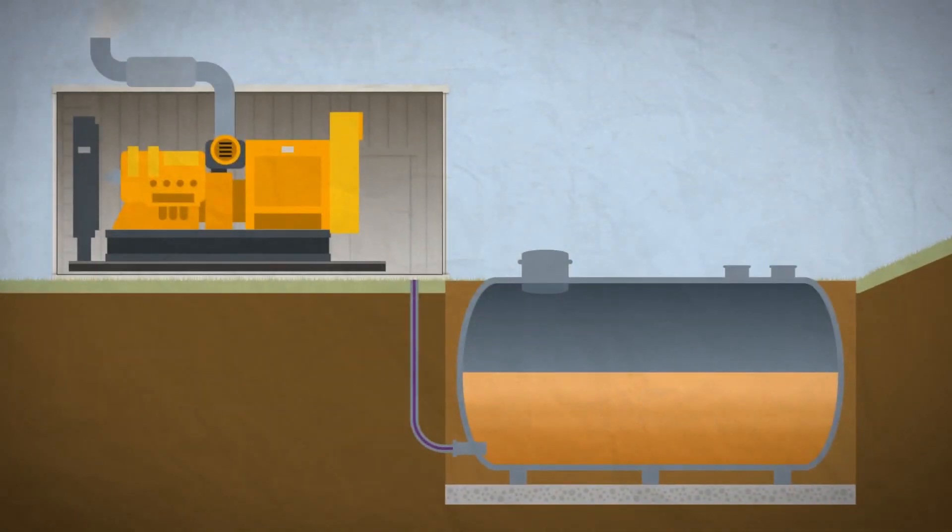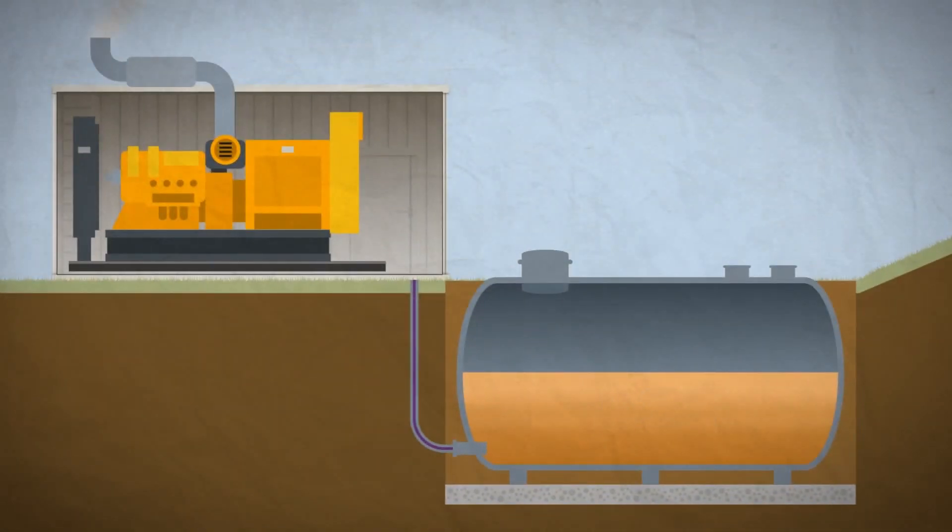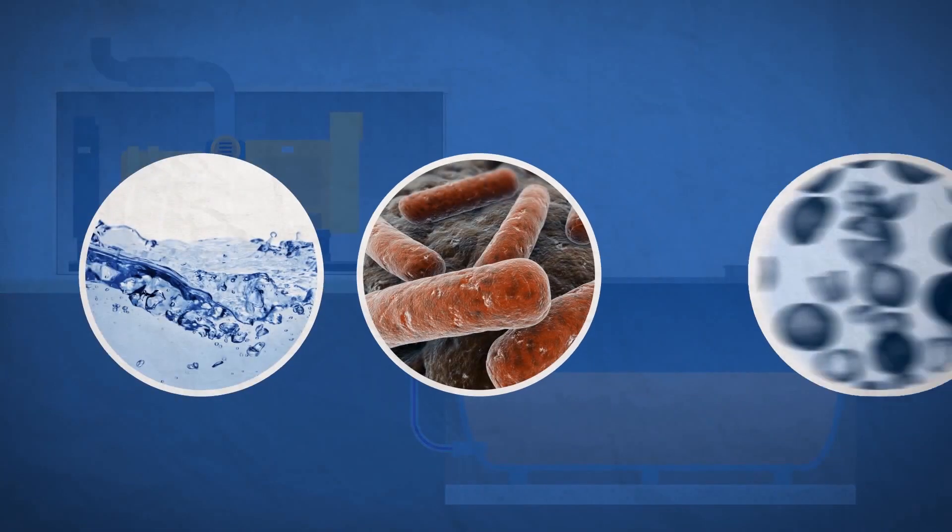It's now widely accepted that if stored under normal conditions, diesel will remain in a usable condition for just 6 to 12 months. As it gets older, diesel suffers from three main types of contamination: water, bacterial growth or diesel bug, and solid particulates.